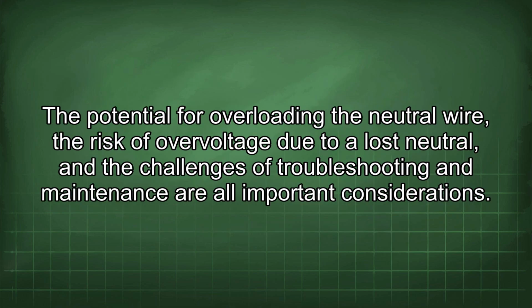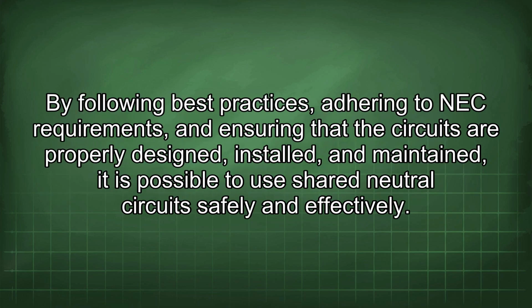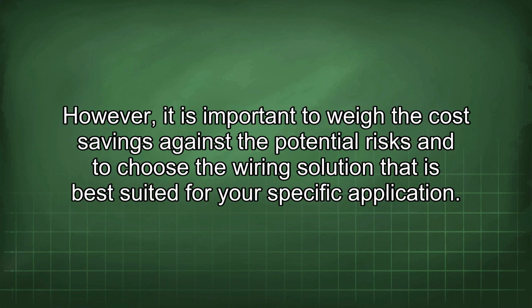The potential for overloading the neutral wire, the risk of overvoltage due to a lost neutral, and the challenges of troubleshooting and maintenance are all important considerations. By following best practices, adhering to NEC requirements, and ensuring that the circuits are properly designed, installed, and maintained, it is possible to use shared neutral circuits safely and effectively. However, it is important to weigh the cost savings against the potential risks and to choose the wiring solution that is best suited for your specific application.